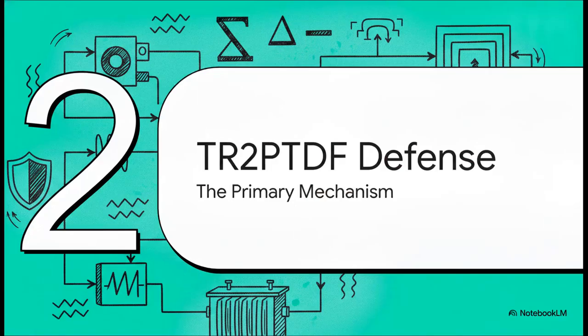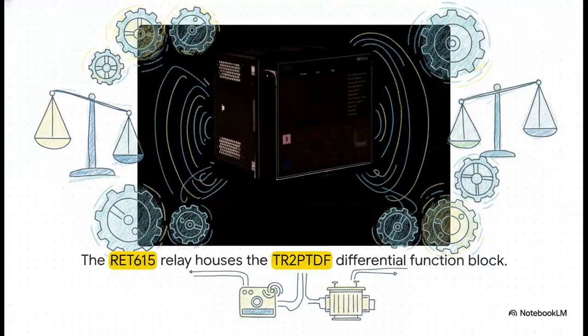Moving on to Section 2, TR2PTDF, the primary defense. Now, let's look at the actual hardware executing this. This is the RET615 relay. This compact little unit is essentially the physical brain of the operation. Inside this device runs a specific mathematical function block known as TR2PTDF. This function is the life-saving calculator that's continuously executing the balance scale logic we just talked about. It is the primary defense for generator transformer blocks.